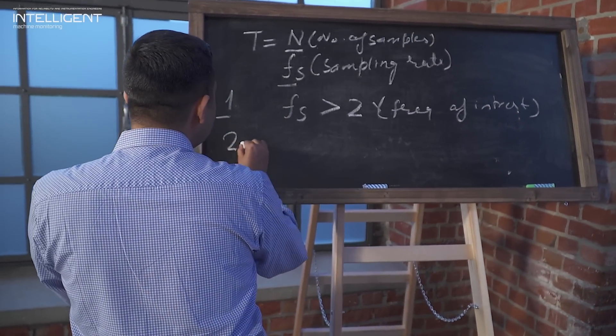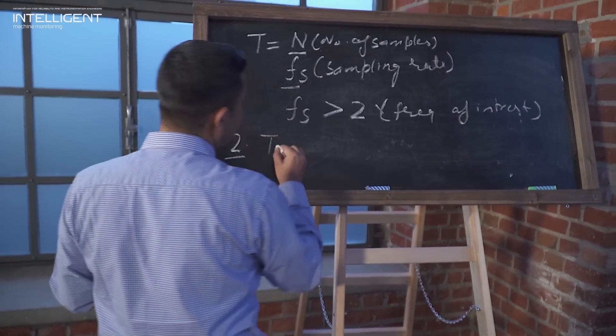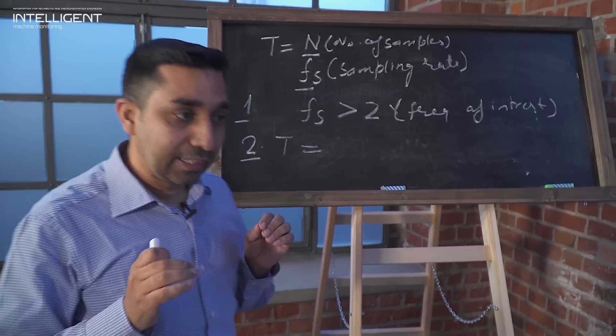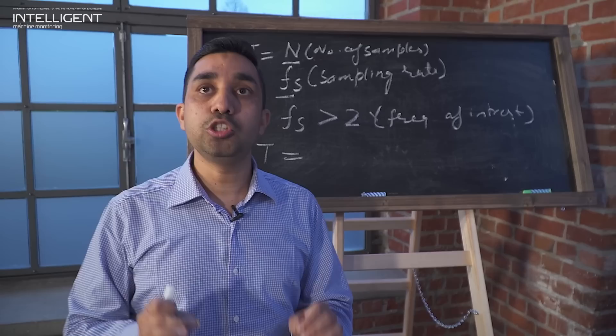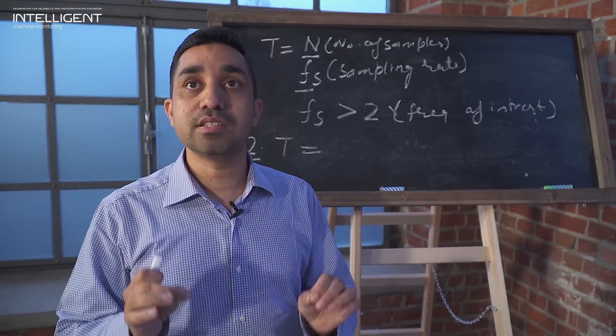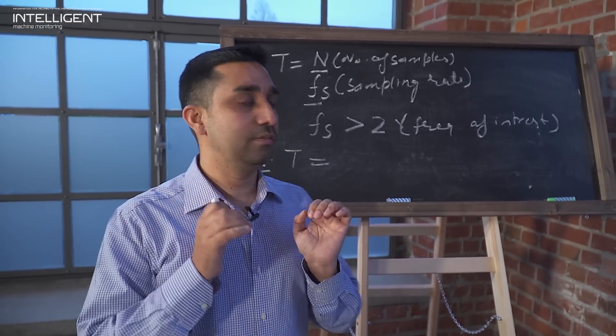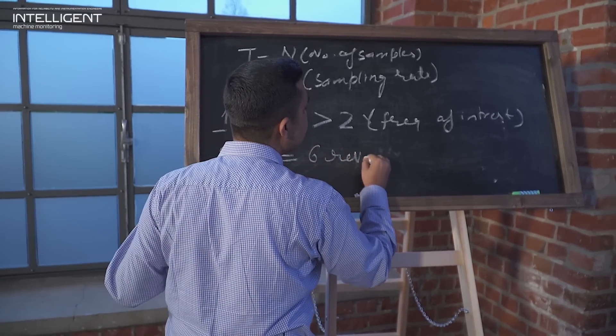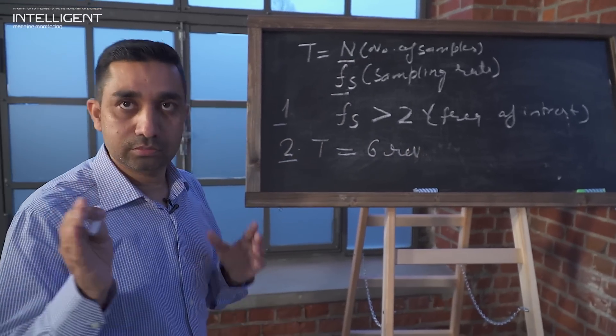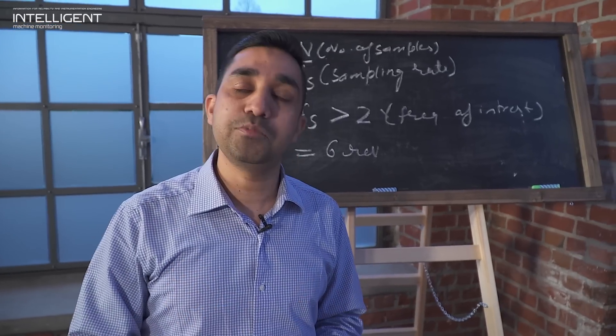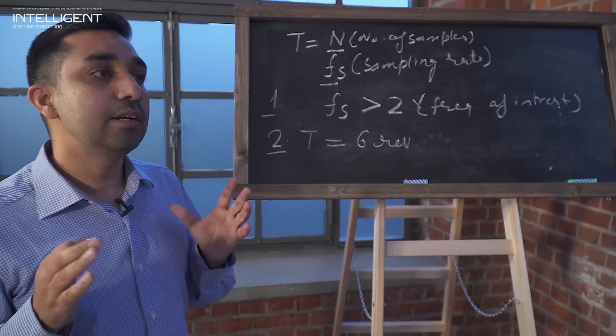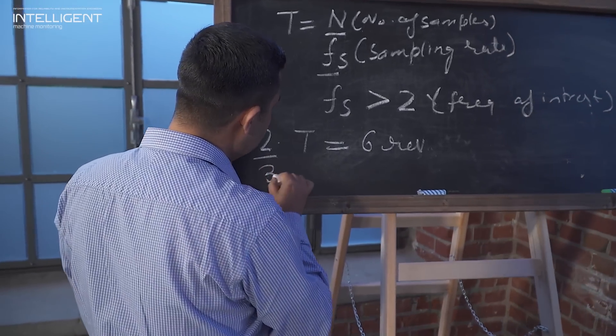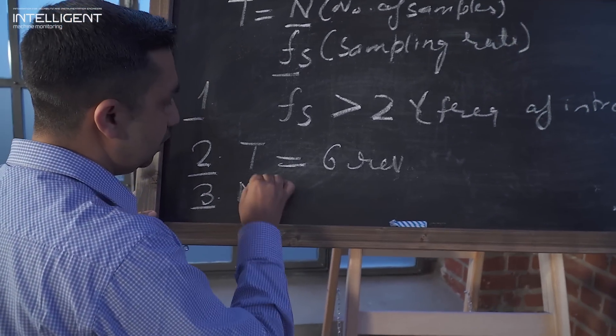Second rule for the time period. Your time period should be at least able to capture six shaft revolutions. At least minimum of six revolutions you should capture in the time signal.